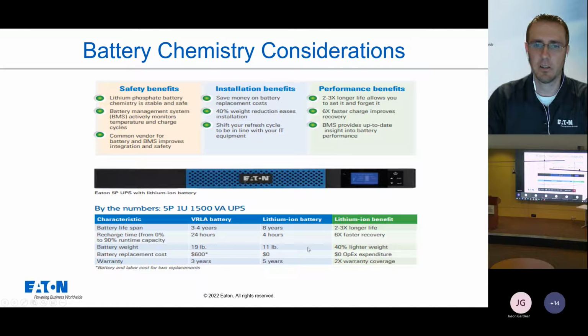You're not going to replace the lithium ion batteries, at least not in these plug and play units. With a VRLA, you should be replacing it every 3 or 4 years, though not everybody does that. But if you think about replacing every 3 or 4 years, that's 2 to 3 battery replacements over an 8 to 10 year period, so you're going to be spending $600 plus. That's an old dollar amount before inflation, I'm sure it's much higher now, whereas the lithium ion battery is there for 8 to 10 years, good to go.